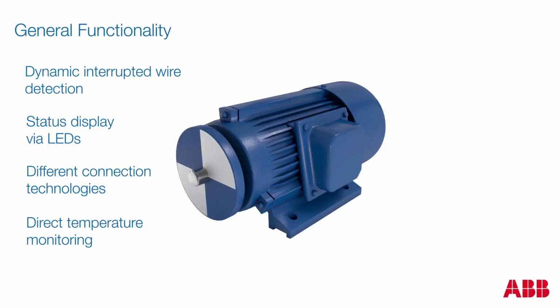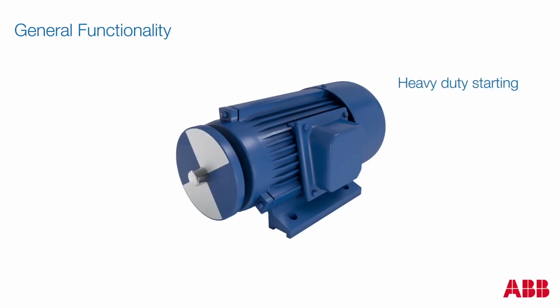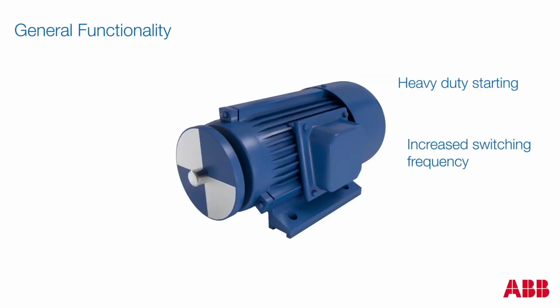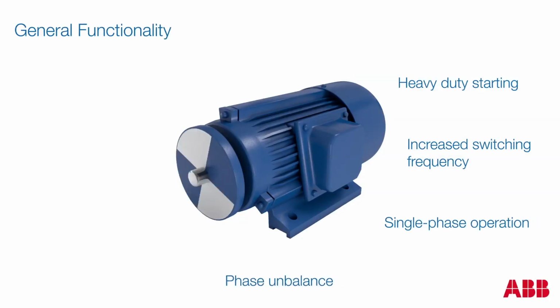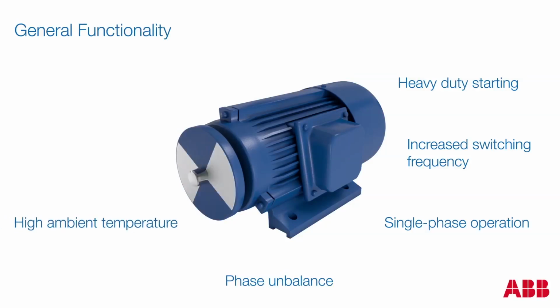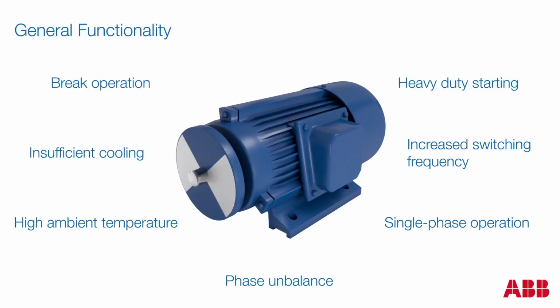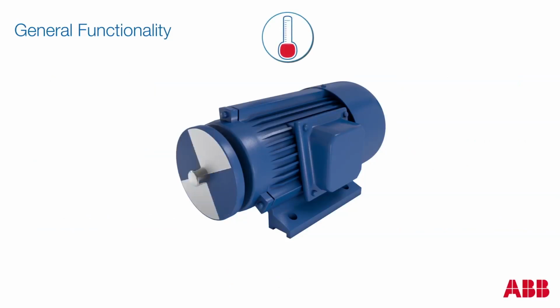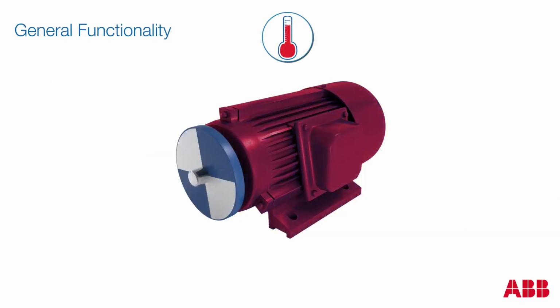motor itself. This enables direct control and evaluation of the following operating conditions like heavy-duty starting, increased switching frequency, single-phase operation, phase unbalance, high ambient temperature, insufficient cooling, braking operation. The direct measurement of the real motor temperature protects the motor consequently from overheating and its consequences.